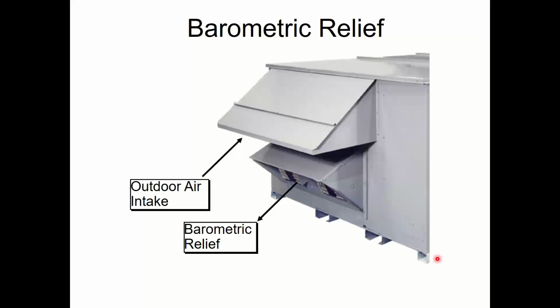There are lots of possible pathways. The most common ones are to do it with the same rooftop that's sucking the air in. And the most common way to do that on a small, simple system is a barometric relief. What is a barometric relief? It's just a piece of sheet metal hanging there. And when the pressure in the building builds up, instead of pushing the front door open, it pushes this damper blade open. That's it. It's not anything smarter than that. That's why we do it on most systems.